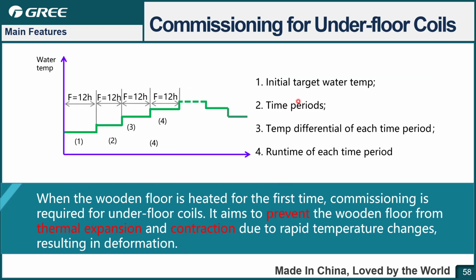Next one is the commissioning for the underfloor coils. For the floor heating, the coil is installed below the floor, right? The first time when you start the unit, if you directly heat the water to a very high temperature, in this case due to the thermal expansion and contraction, the floor may be deformed. Yes, it may be deformed because of the temperature change.